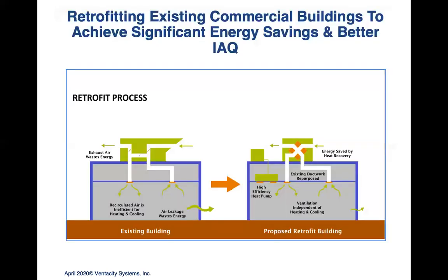So in a nutshell, the model we're going to talk about today is very simple. It's a retrofit for HVAC. Typically, what you've got on the left is a packaged rooftop unit. At the end of life, when those rooftop units are due to be replaced, rather than replacing it with another rooftop unit, you replace it with very high efficiency heat recovery ventilation, which I'll really talk about today, as a dedicated outdoor air system. And then you have heat pumps of one form or another. In most cases, that has been a VRF type heat pump system to replace the formerly RTU systems on the roof.